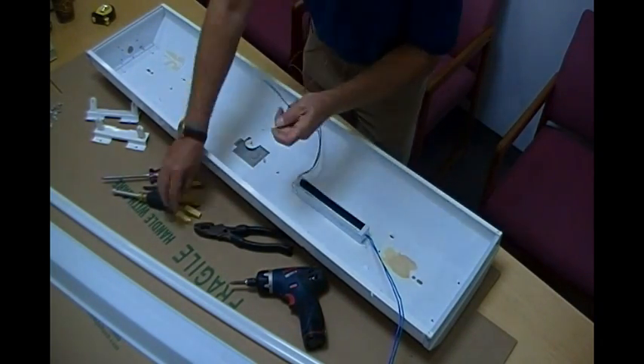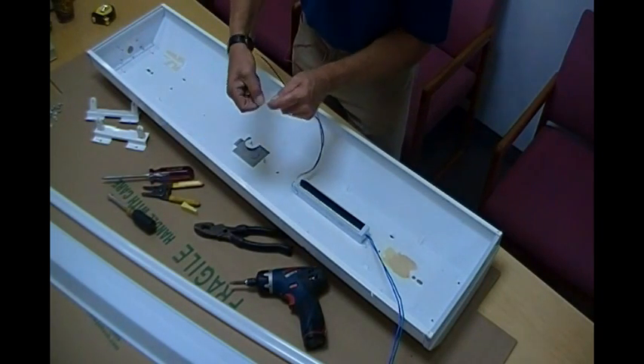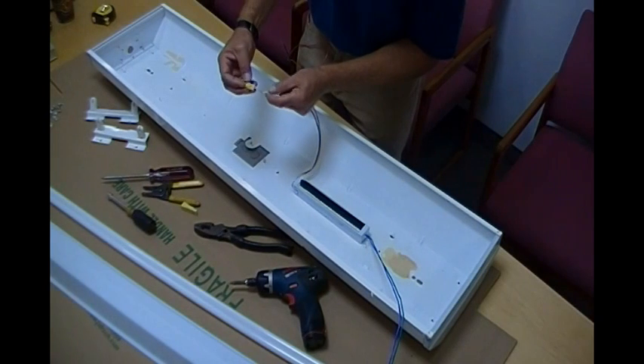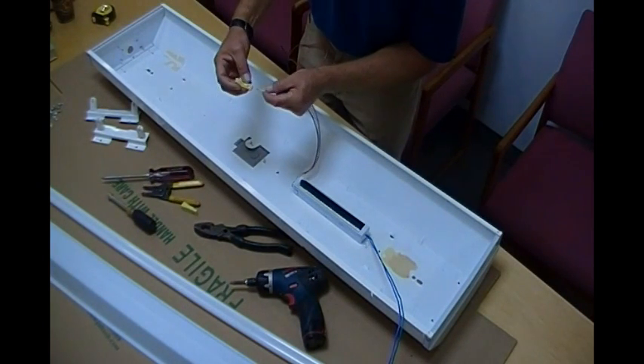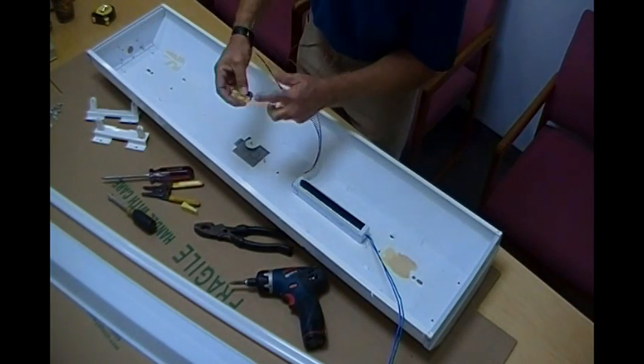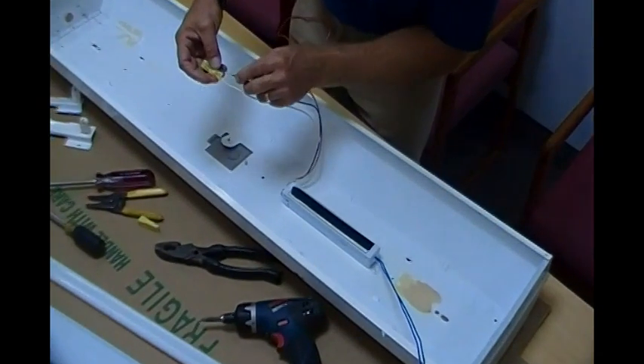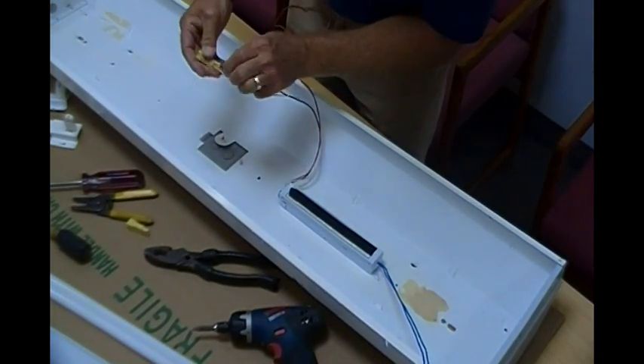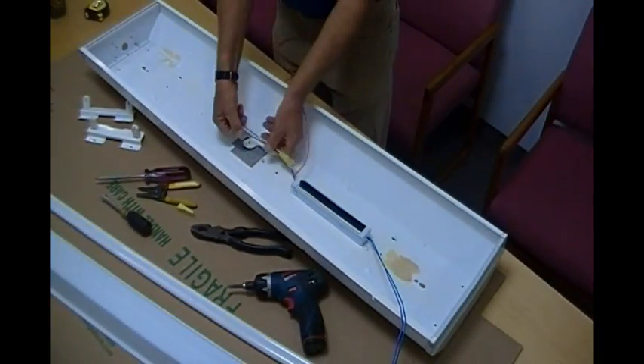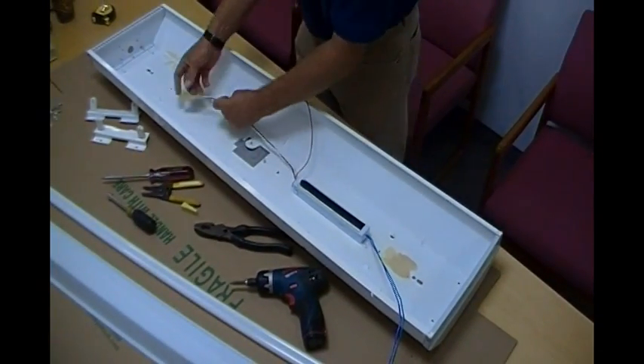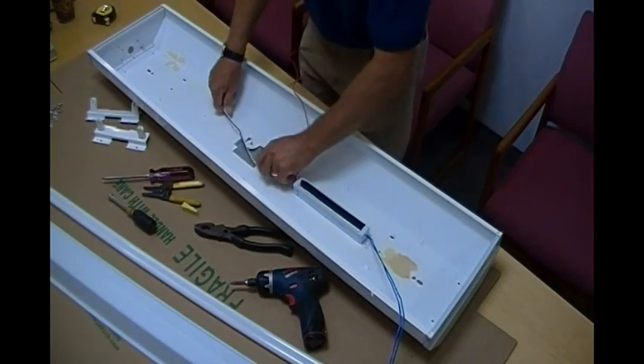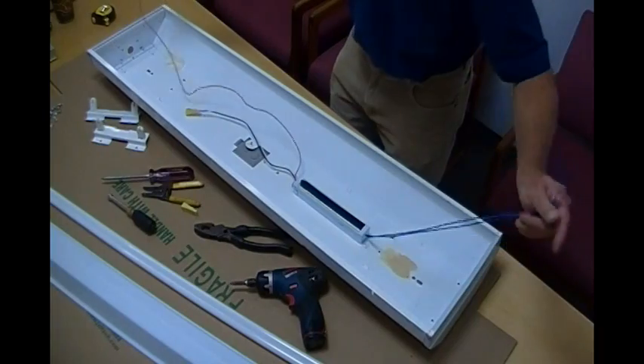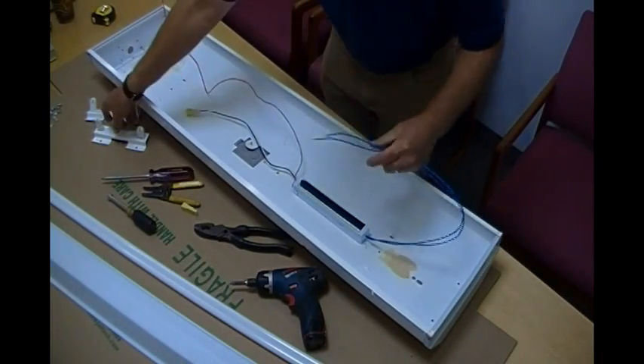Be sure to attach your certified required ballast disconnect for 347 volts. It's required on any installation above 150 volts and that will be attached to your power feed when you finalize putting on your socket plates for the T5.